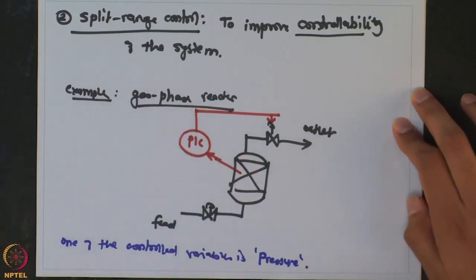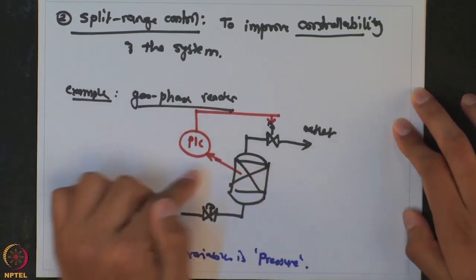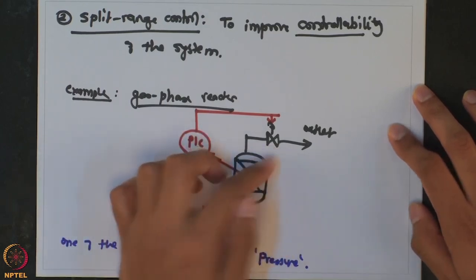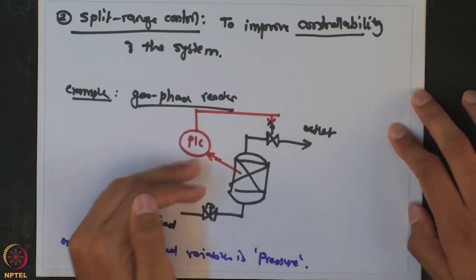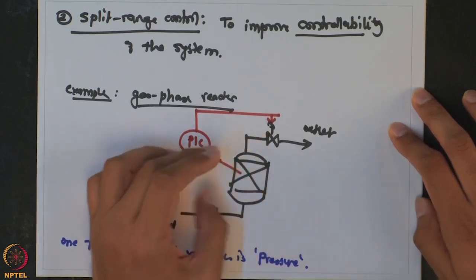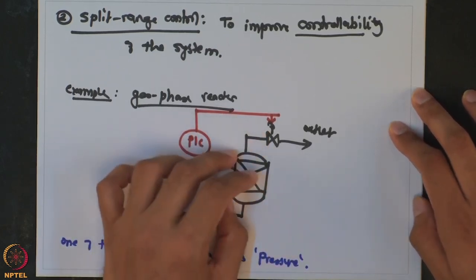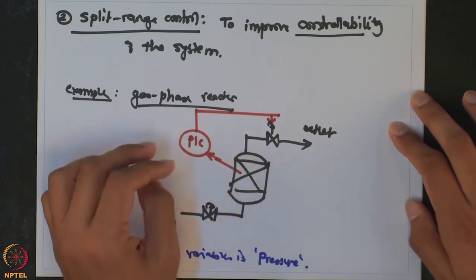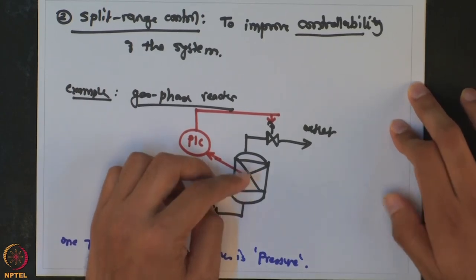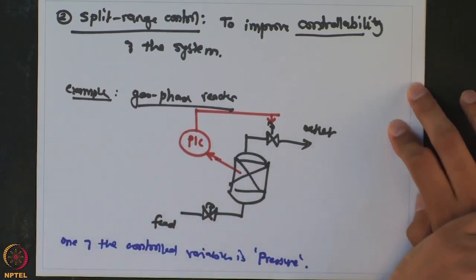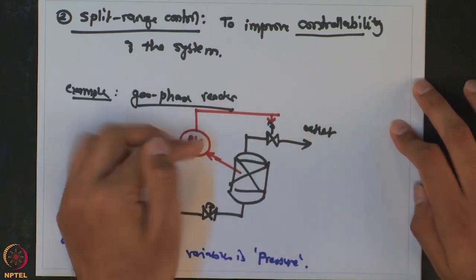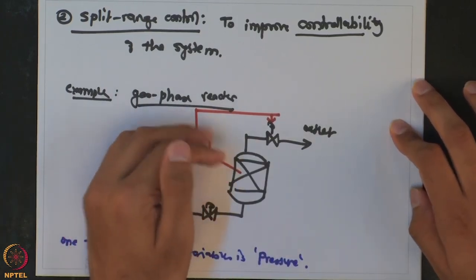Under normal circumstances, this pressure controller works as follows: if the pressure slightly goes above the value, the outlet valve will open; if the pressure starts to drop, you close the outlet valve so the vapor inventory inside the reactor is maintained. Now let us consider an abnormal situation where the reactions inside the reactor go into a runaway, generating a lot of vapor and causing the pressure to keep increasing.